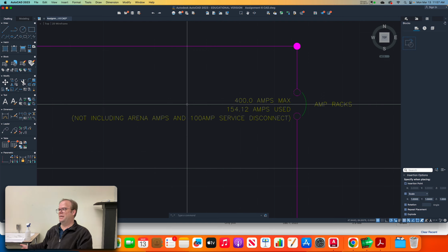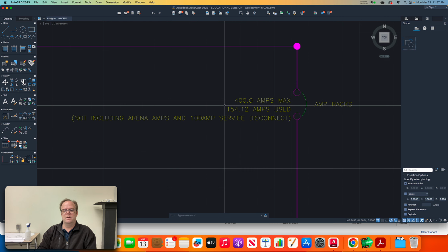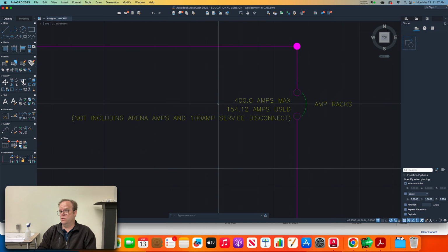Potentially, someone could walk in the building and tie in a bunch of feeder cable into that company switch on the stage and pull 100 amps off this thing. I'm not doing that. Somebody could, though. So I certainly want to make sure that whatever I'm using is 100 amps less than the max, just because I know somebody could come and do that.